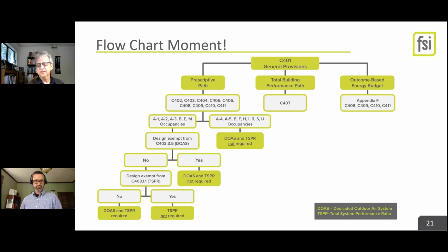But since we got an engineer on the call, he of course made us a flow chart. Had to flow chart it. So when we're thinking about this, and this is a little preview for what we're about to talk about, the prescriptive path, you've got all of the things basically except C407 in chapter 4. Then based on your occupancy, you get kicked into doing a dedicated outside air system, DOAS, and TSPR, total system performance ratio, down in that bottom right corner. We're spelling out our terms. We'll do all of this in more detail, but basically, if you flow chart this out based on your occupancy and whether you need DOAS and or TSPR, you end up with different requirements and different system minimums you must meet. So it's something you want to hire somebody who has worked in Washington State and knows this, so you're not learning the learning curve with them.